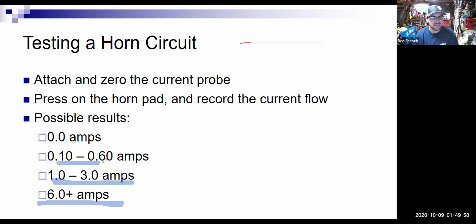What do you think about this little tiny bit of current flow? Let's say I'm only moving like 0.5 amps. That's still some current flow, but it's not very much -- less than 1 amp. What do you think is going to take about 0.5 amps? Well, a relay would take maybe about half an amp if I was just running the relay. So if I was at this scale, I would think, maybe the relay's clicking, but maybe the actual contacts of the relay aren't closing, or something else is going wrong.